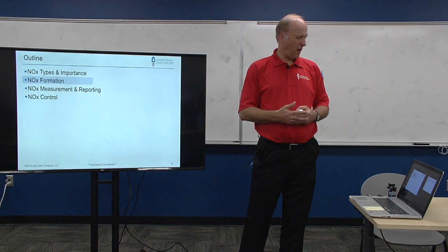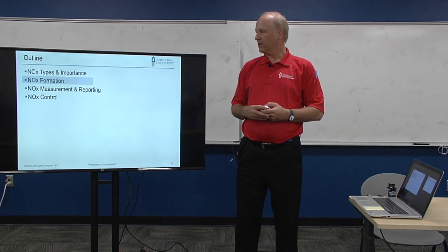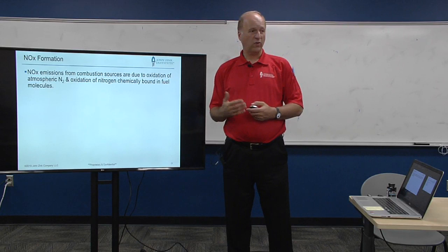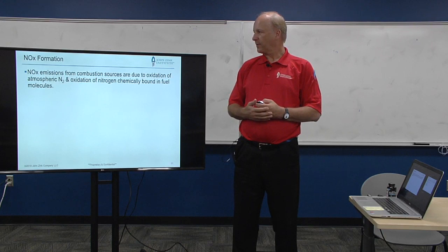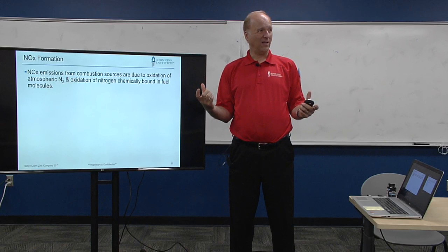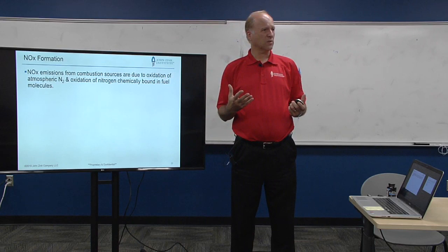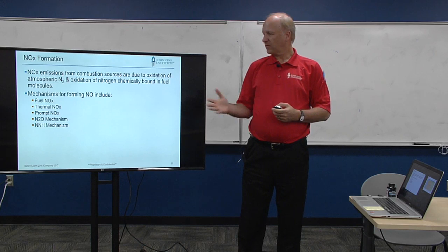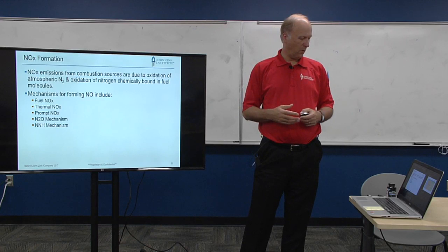Let's talk briefly about how NOx forms. The regulators honestly don't care how it's formed — they just want to know how much is coming out. But if we understand how it forms, we can control it better. NOx emissions are primarily due to oxidation of atmospheric nitrogen. If you have organically bound nitrogen in your fuel, that's a more complicated process, but most NOx is generally made by N2 and O2 at higher temperatures reacting to form NOx. There are more than three kinds of NOx, but the first three mechanisms are the most important for typical combustion processes, and the other two are for more specialized processes.